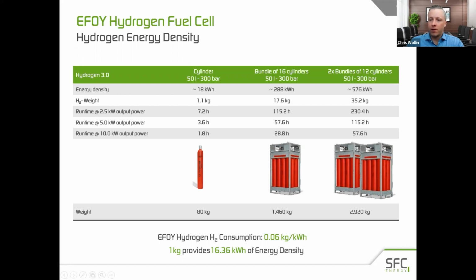So overall, our EFOY hydrogen fuel cells consume roughly 0.06 kilograms of hydrogen per kilowatt hour of energy produced, meaning that every 1 kilogram of hydrogen provides just over 16 kilowatt hours of energy production. The standard type 1 steel 50-liter cylinders at 300 bars contain just over 1 kilogram of hydrogen. And this amount can vary depending on the bottle pressure, which can range anywhere from 150 to 350 bars for the type 1 cylinders.